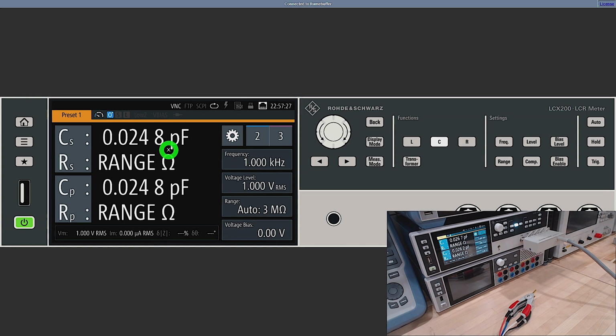Now remember that this open correction is really only meaningful if the capacitances you're trying to measure are comparable to these parasitic capacitances initially. The capacitors I want to measure next are not, but nonetheless it's important to know how to do this. You can similarly do the same thing for the short correction as well, which will give you much better resistance measurements.